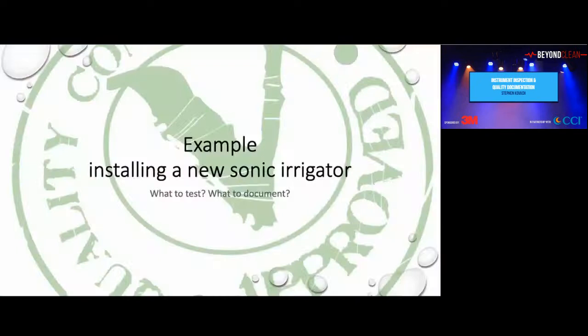Examples: installing a new sonic irrigator, what to test and what to document. So we know the standard says that when you have a sonic, you should check for cavitation, external surface cleaning, and if you have lumens, the ability to clean lumens. We are just going to do one critical parameter, and this one is just cavitation.